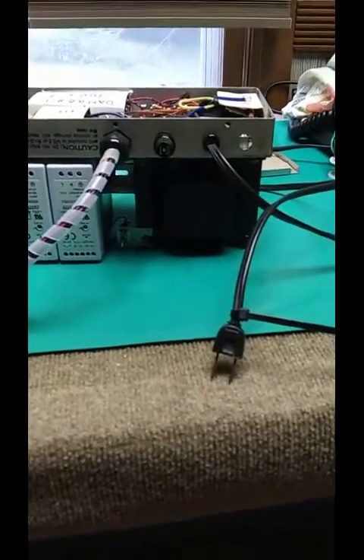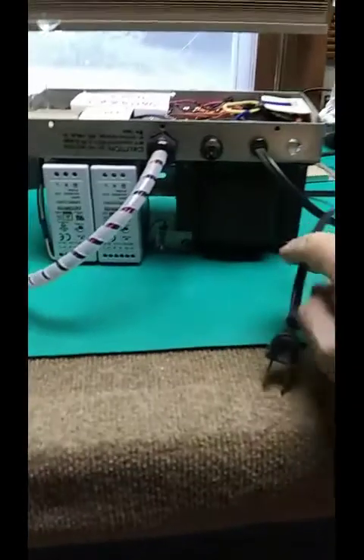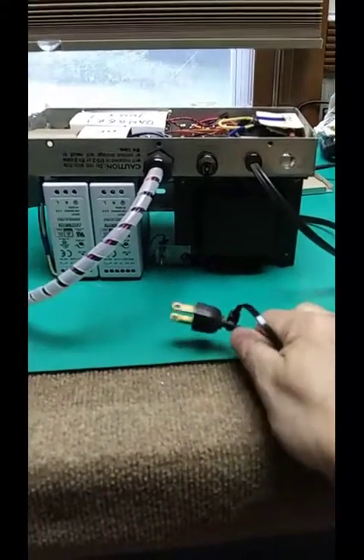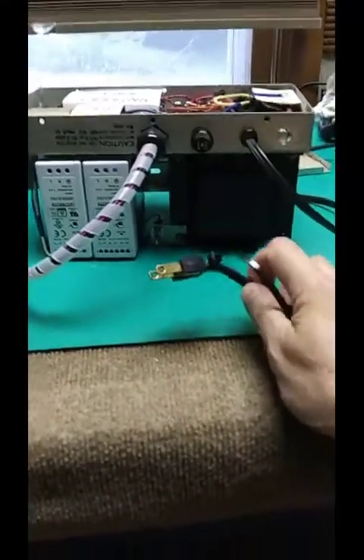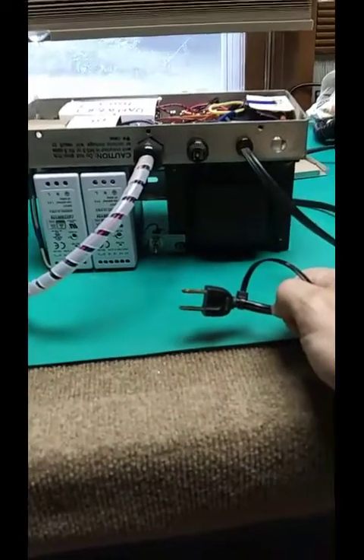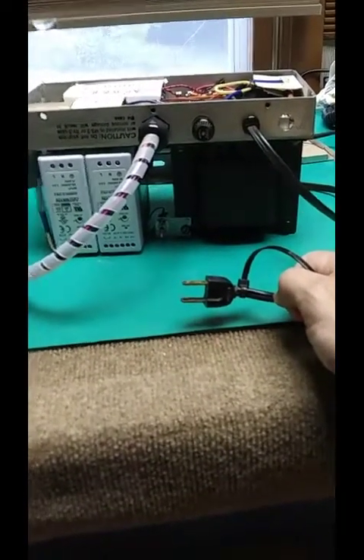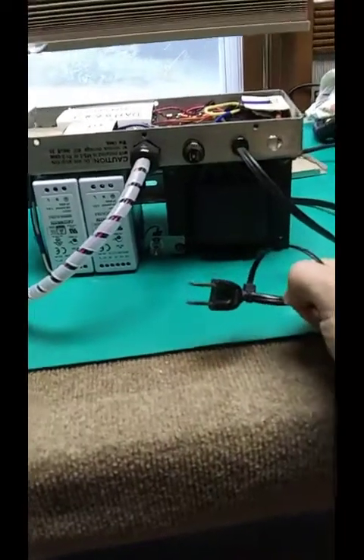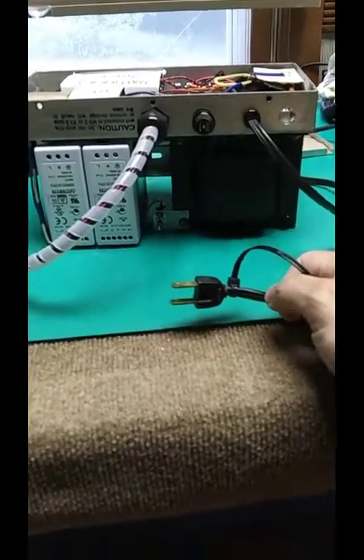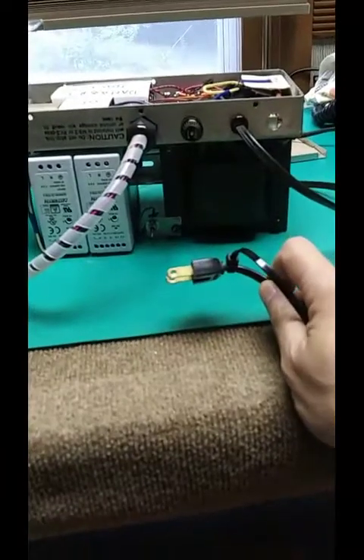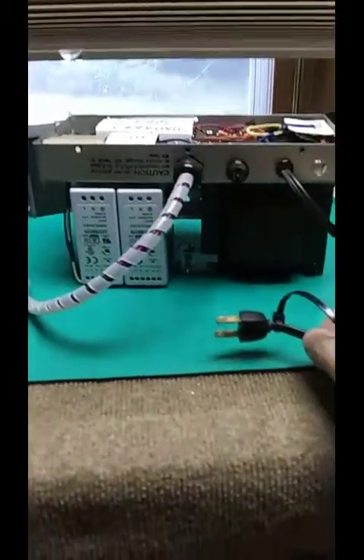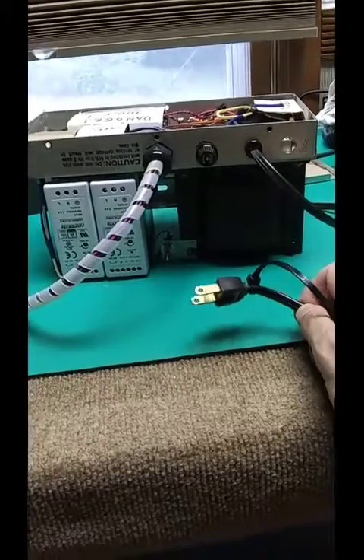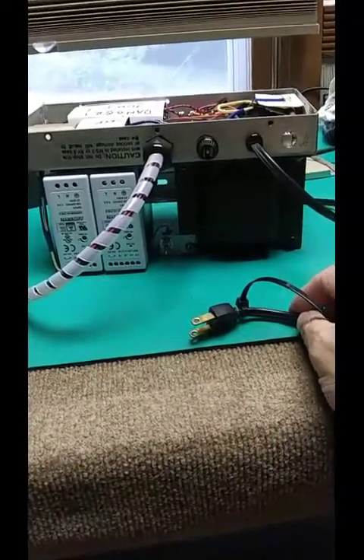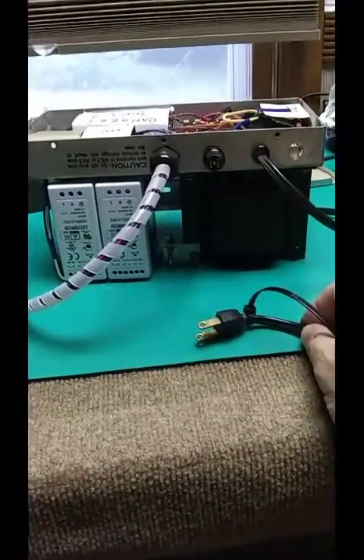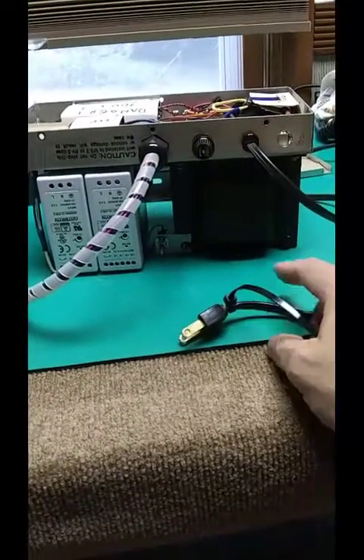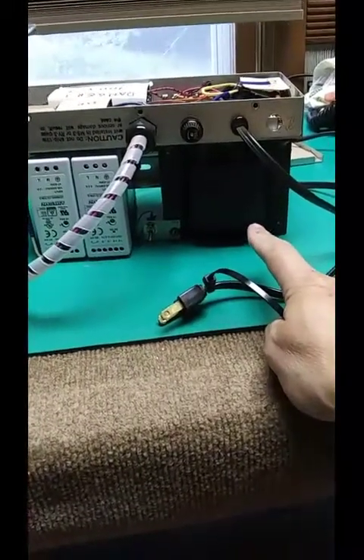K8BYP with a serious power supply no-no. Some of us think we know what we're doing, and make the mistake of putting grounded cords on these because they have fallen for the myth that everything must be grounded. The engineers at Drake that put that 2-prong unpolarized cord on this power supply had a reason for it. I absolutely do not put a 3-wire grounded cord on it, and do not ground that cord to the chassis, because doing so defeats any isolation that might be in that transformer.